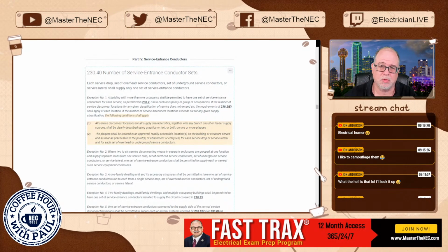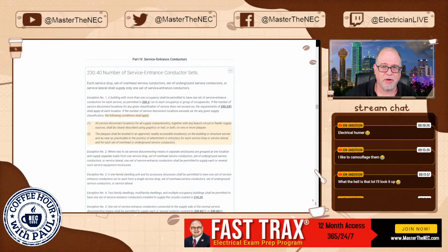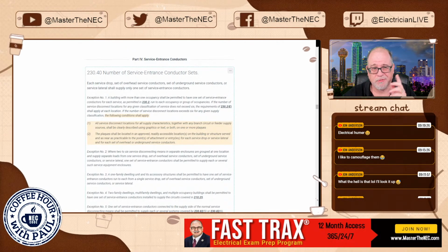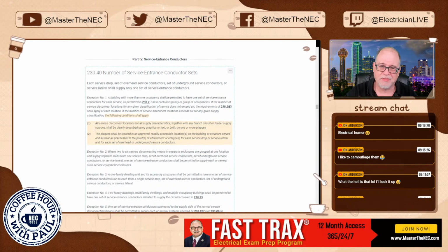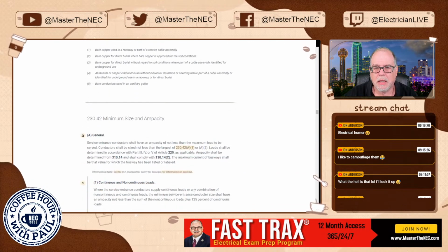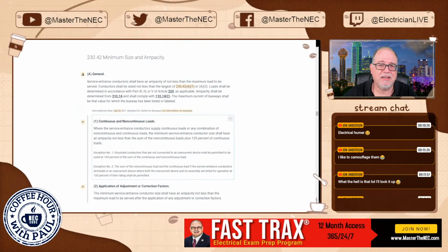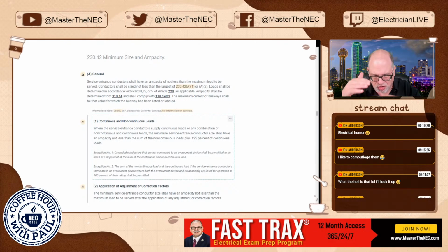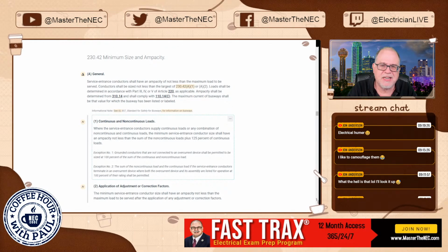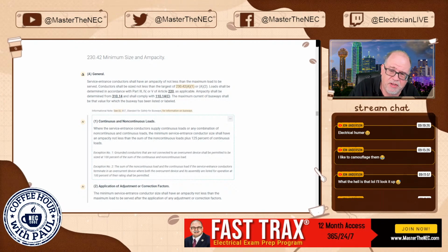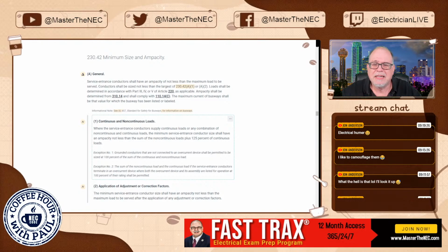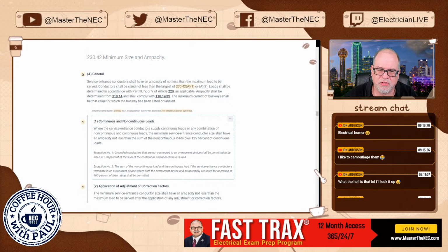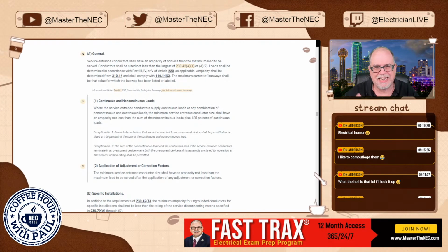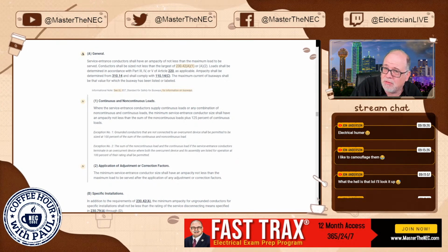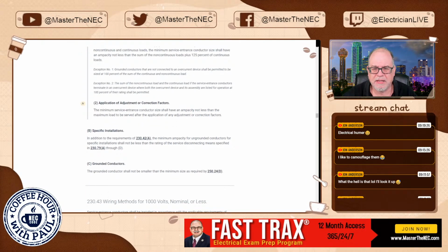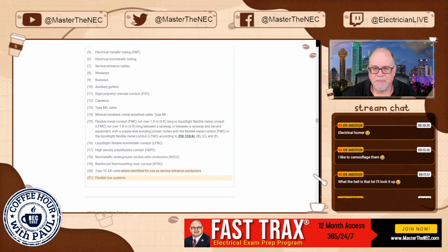So this is just a labeling rule. It didn't change the intent of 230.40. And I have a separate podcast or video available out there that explains the nuances of 230.40 if you're interested in that. Let's see here. Ampacities, this didn't change. It's just changed the structure and broke it out so that we know that continuous loads and non-continuous loads, again, 125% of continuous loads, 100% of non-continuous loads. And then, of course, if you're applying adjustment and corrections, didn't change, it just broke it out. So it's kind of similar to how it's done now in 210.19 for branch circuits. Let's see here.